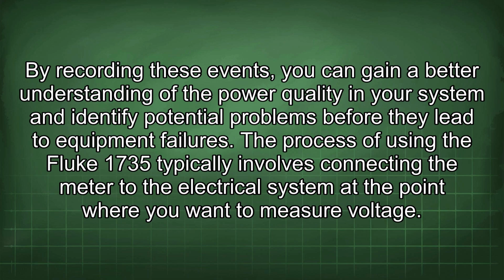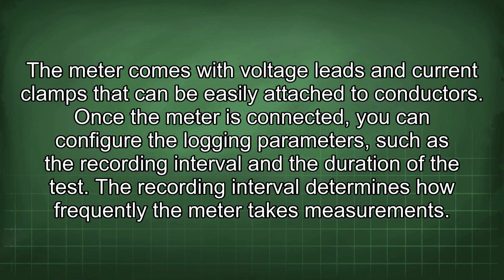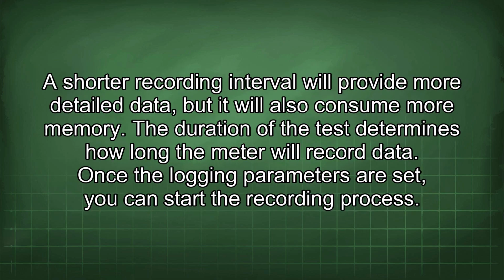The process of using the Fluke 1735 typically involves connecting the meter to the electrical system at the point where you want to measure voltage. The meter comes with voltage leads and current clamps that can be easily attached to conductors. Once the meter is connected, you can configure the logging parameters such as the recording interval and the duration of the test. The recording interval determines how frequently the meter takes measurements. A shorter recording interval will provide more detailed data, but it will also consume more memory. The duration of the test determines how long the meter will record data.